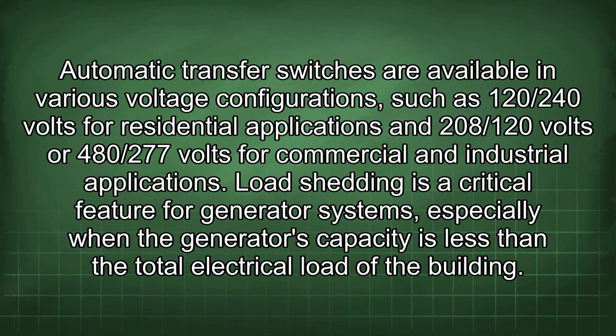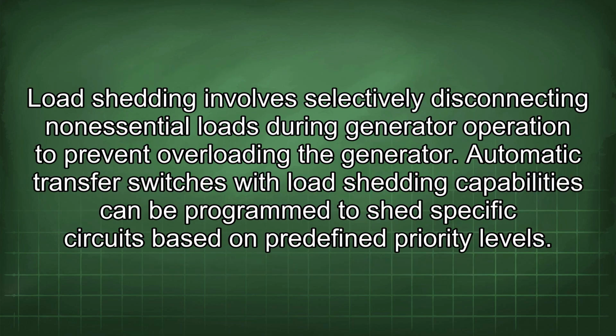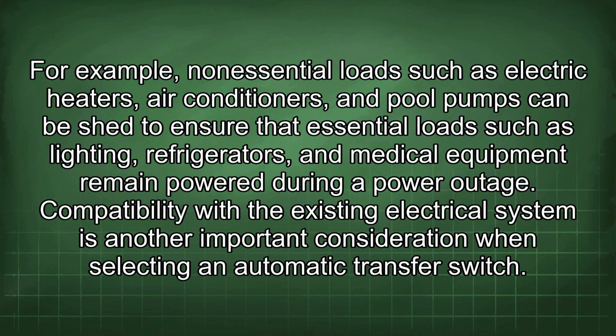Load shedding is a critical feature for generator systems, especially when the generator's capacity is less than the total electrical load of the building. Load shedding involves selectively disconnecting non-essential loads during generator operation to prevent overloading the generator. Automatic transfer switches with load shedding capabilities can be programmed to shed specific circuits based on predefined priority levels. For example, non-essential loads such as electric heaters, air conditioners, and pool pumps can be shed to ensure that essential loads such as lighting, refrigerators, and medical equipment remain powered during a power outage.